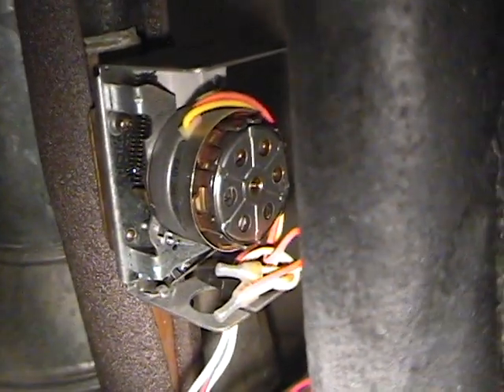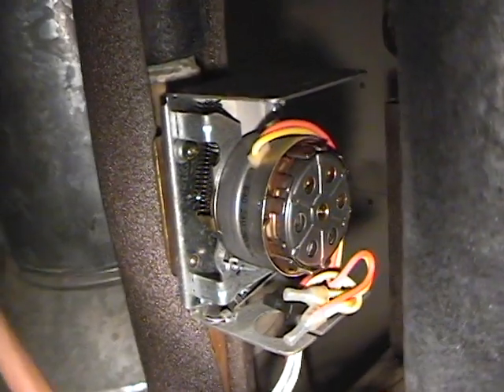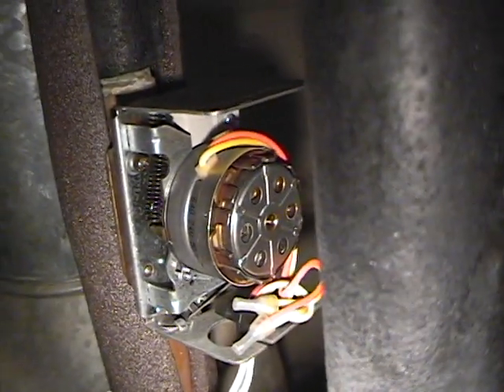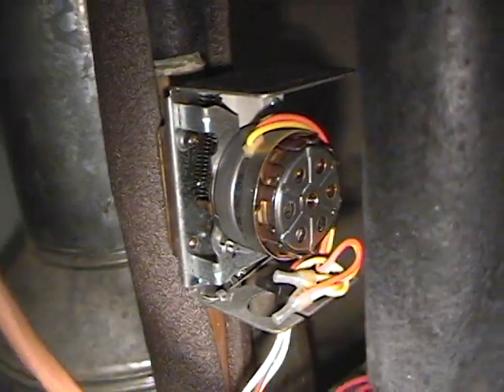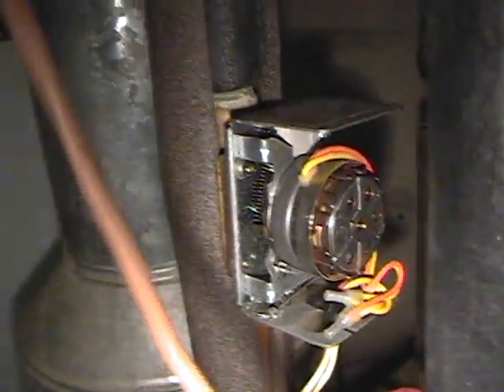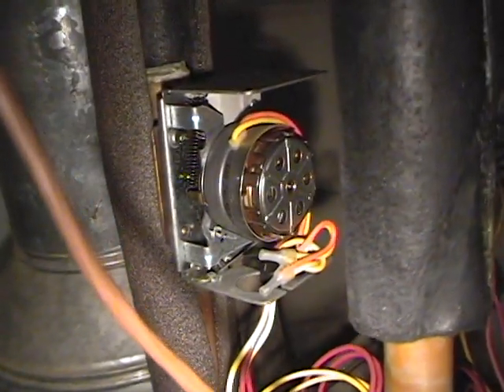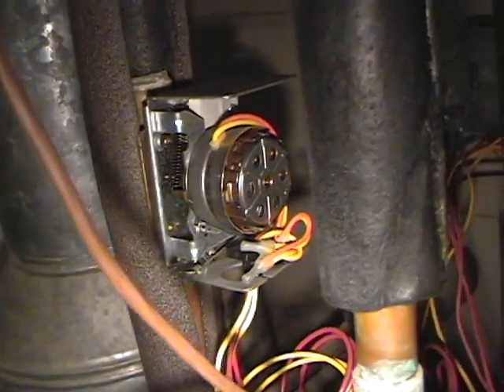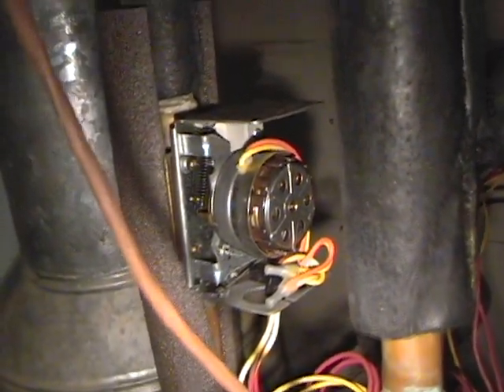So right now, like I said, the windings are holding the disc in place, going against the springs, and as long as the valve is open like that, the boiler will run. So it's kind of like a safety device where, if we were to lose power, it would just shut off all electrical connections and the valve would close. So it's good that it works that way.